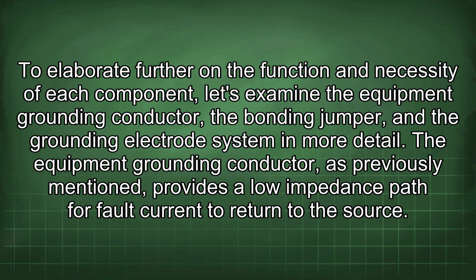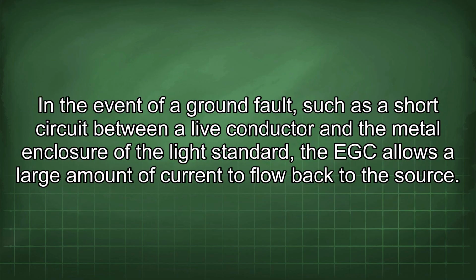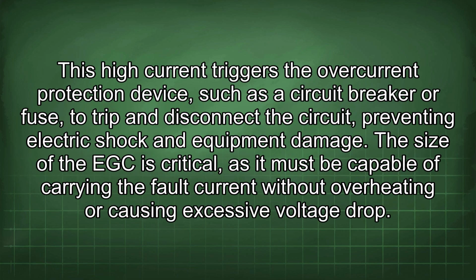The equipment grounding conductor, as previously mentioned, provides a low impedance path for fault current to return to the source. In the event of a ground fault, such as a short circuit between a live conductor and the metal enclosure of the light standard, the EGC allows a large amount of current to flow back to the source. This high current triggers the overcurrent protection device, such as a circuit breaker or fuse, to trip and disconnect the circuit, preventing electric shock and equipment damage. The size of the EGC is critical, as it must be capable of carrying the fault current without overheating or causing excessive voltage drop.